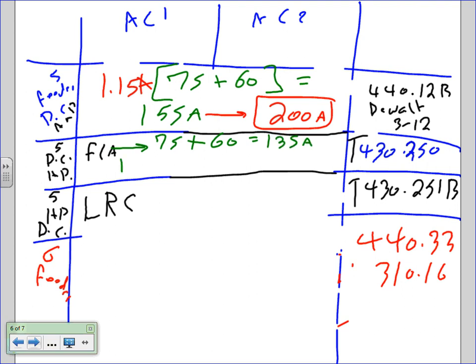Okay? Then you take the 135 amps to table 430.250, because it's full load amps. This will translate into 125 horsepower equivalent. Let me repeat myself. You add the two full load amps, 135. Take the 135 to table 430.250 under 480 volts. That will translate into 125 horsepower. So that's the first horsepower rating.